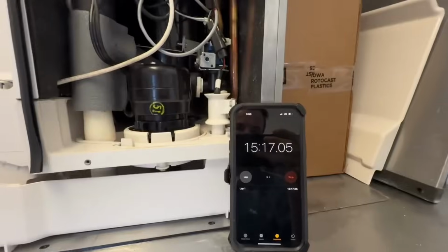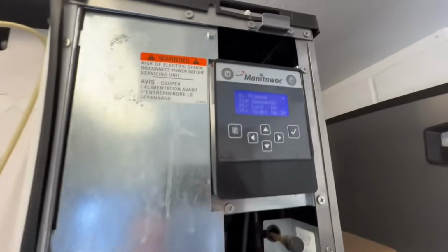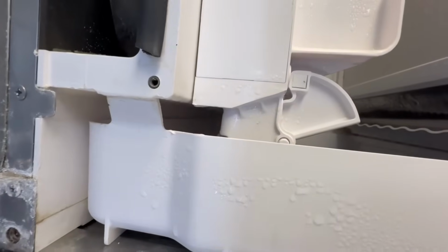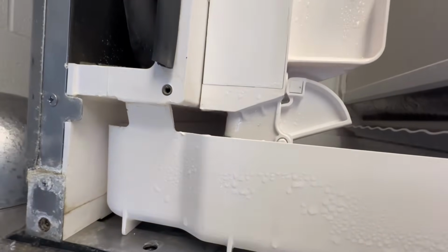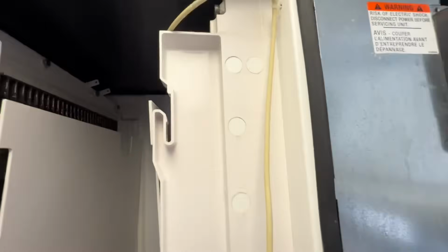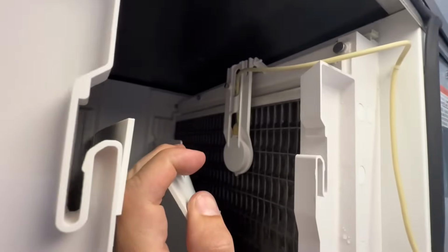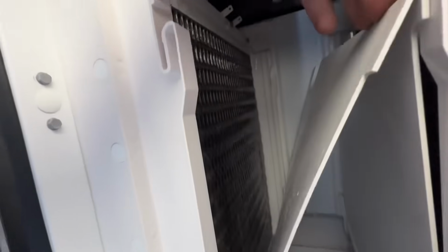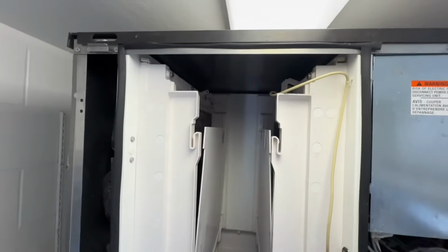Let me speak to the customer, see if she wants me to swap out these water filters or not. 15 minutes into freeze, still not sensing water, and water inlet valve is still energized. Kind of crazy. I think we're actually getting ready to go into harvest based off the amount of ice that's built up.